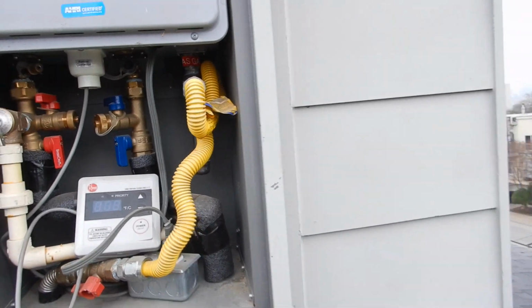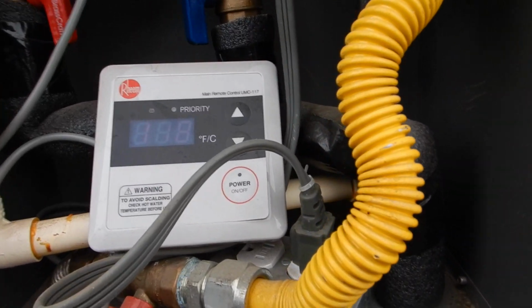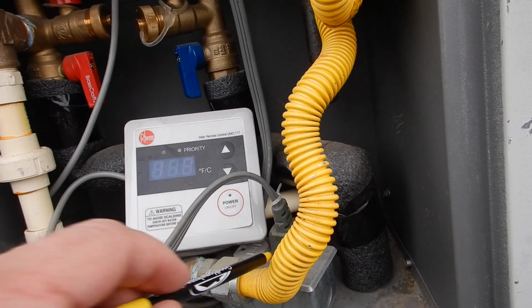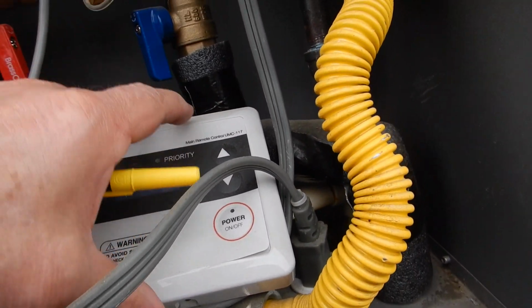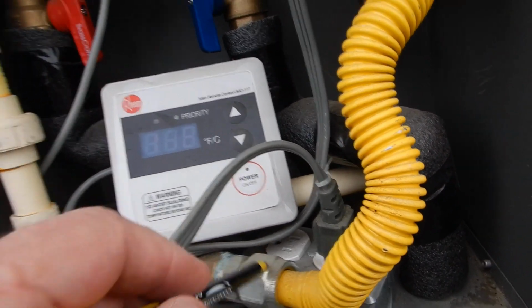Okay, are you through, bud? No, not by a long shot. Your electric receptacle outlet, you're supposed to have a switch, not just a plug that de-energizes. I get it, I can pull that out, de-energize it, we'll be fine, the mechanic can work on it. Then any water that gets in here, where are we?